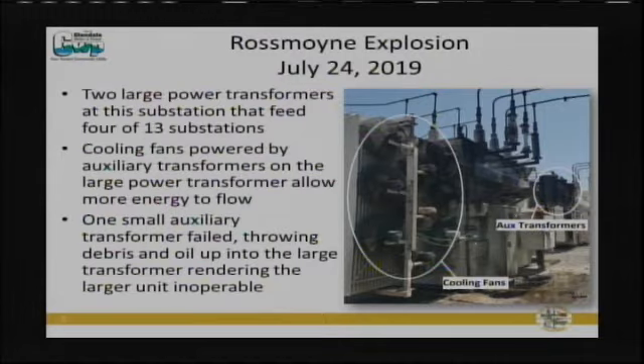So when you look at the larger, almost looks like a building, that's the main substation transformer. So it's quite a bit different than a transformer that most people may envision or picture, like the cans that are mounted on the poles out on the street. This is a very large, complex transformer. The auxiliary transformer literally exploded, and it sent oil, debris, shrapnel, if you will, throughout the area there. And quite frankly, we had an electrician working at the site at the time. We're very fortunate that he came out of this unscathed.